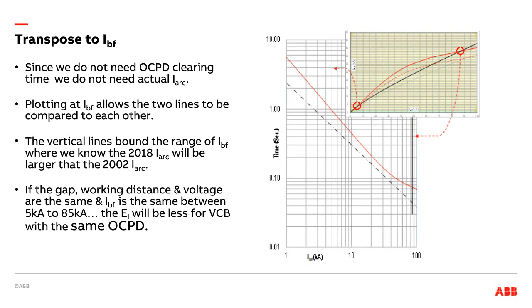So now these two curves can be compared to each other. And just looking at these two, if this is what I calculated in my old study, and this is what I calculated in my new study, whatever PPE selection was good enough for this is going to be good enough for that. My PPE selection is, in fact, relative to the new arc flash study, conservative.